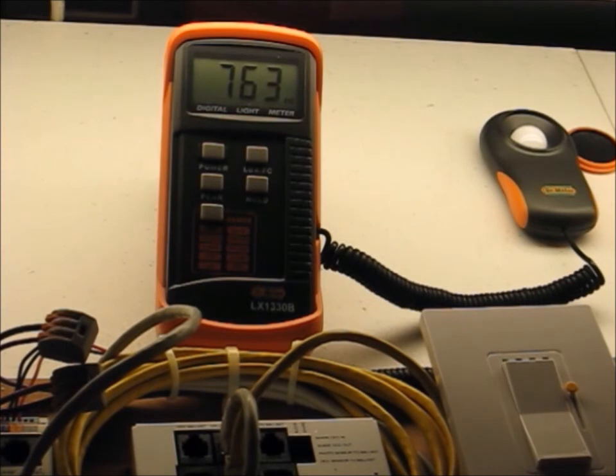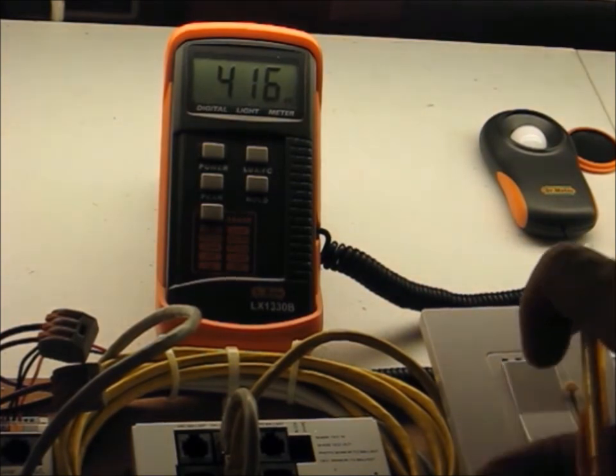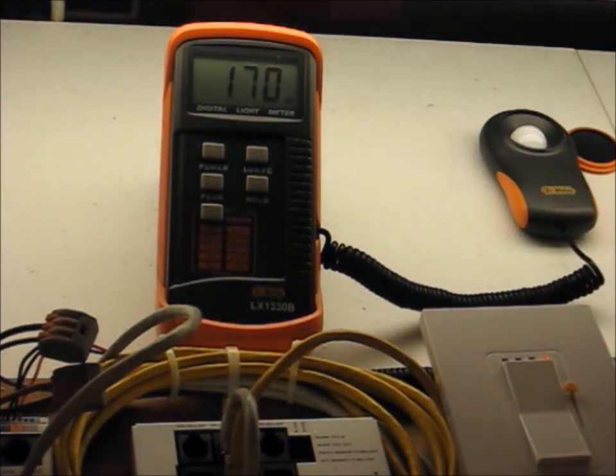So we've got a full output of 763, and our 75 percent dimming allegedly is 613 foot candles. Now I've got 416 foot candles, and now I've got 170 foot candles. I'll take a few readings and average them and then we will crunch the numbers.